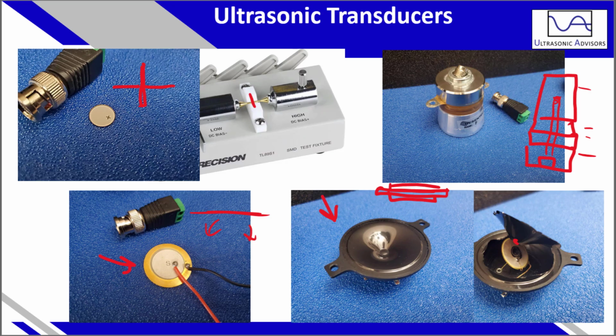Let's take a look at measuring the piezo crystal as seen in the image right here. The crystal is about 10 millimeters wide, and we're going to find that its resonant frequency is quite high. We're going to be loading it into this sample holder held up by 2 pins, while the piezo itself is suspended at its nodal point in the center, which has little displacement. And we will also discuss its significance, and I'm going to move it downward and show you what happens when you don't clamp the piezo at its nodal point.